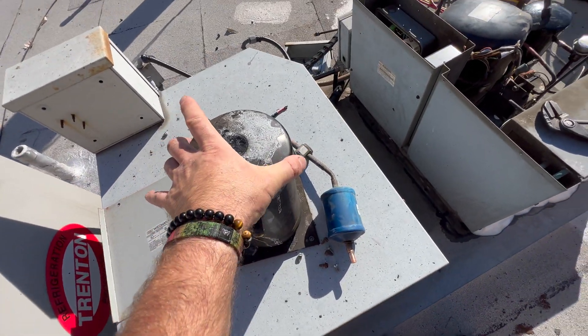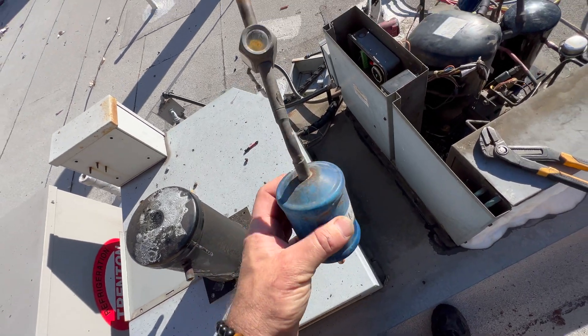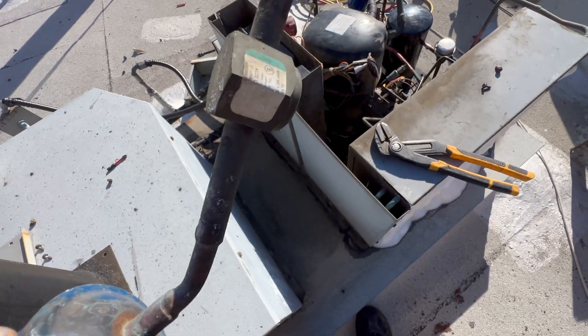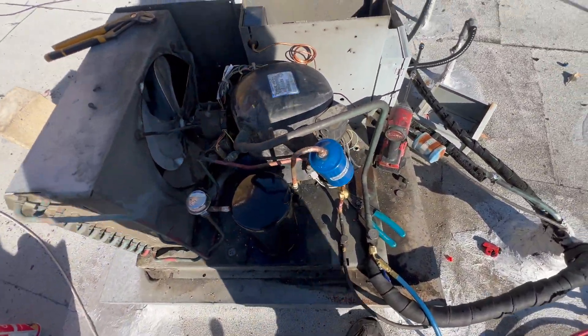This is what this repair was about — the receiver tank is bad. This is how our sight glass was looking: you really can't see anything in there. So we got a new receiver. Had to wait for it for a while.